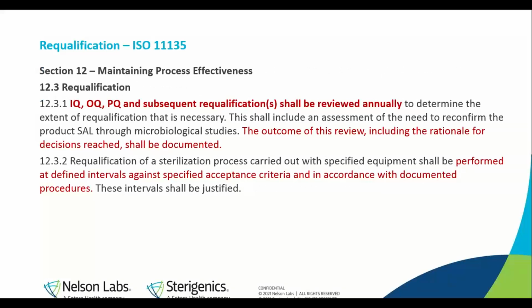Looking at the standard ISO 11135 itself, Section 12 covers maintaining the process effectiveness, and specifically Section 12.3 talks about requalification. And what it says is that the IQ, OQ, PQ, and subsequent requalifications shall be reviewed annually. So that's a requirement to determine the extent of requalification that is necessary. This includes an assessment of the need to confirm the product's sterility assurance level through microbiological studies. The outcome of this review, including the rationale of decisions, should always be documented.